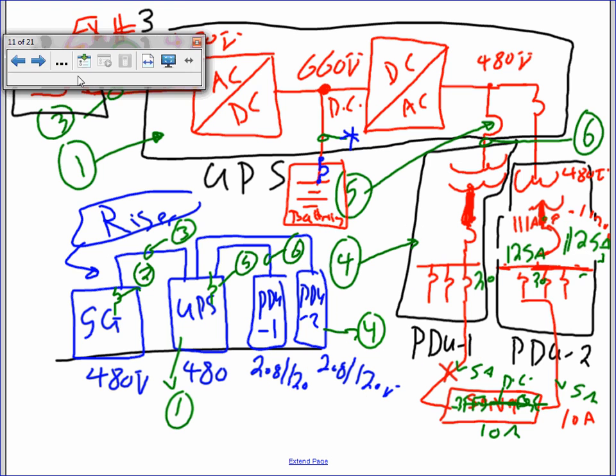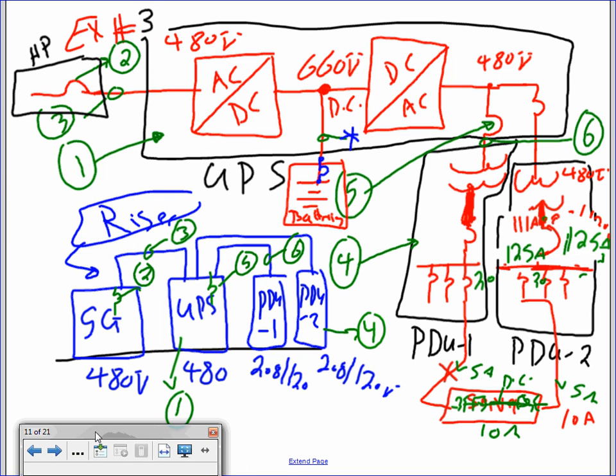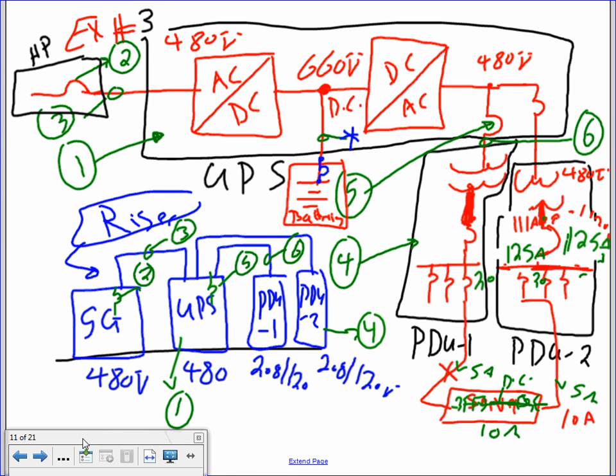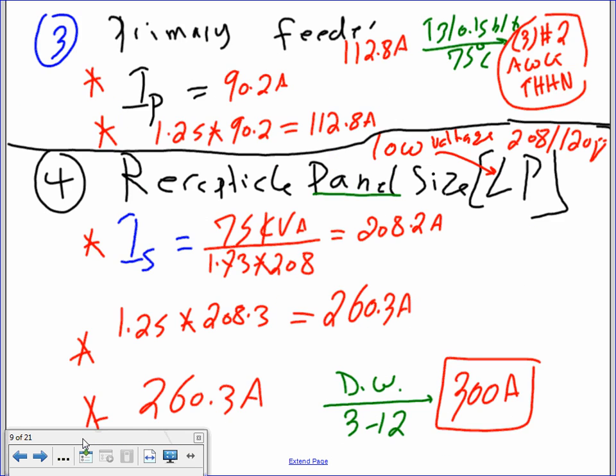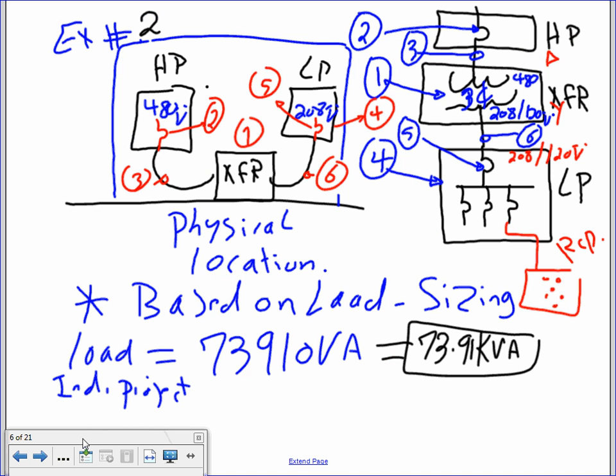Let's go. So now that's basically it, right? We size all these. That's the last one, the receptacle feeders. Now, Adam, my friend, we have another example where we size the receptacle panels, as well as, one more time, a receptacle transformer and receptacle panel fed from a main panel. Any comments, any questions?